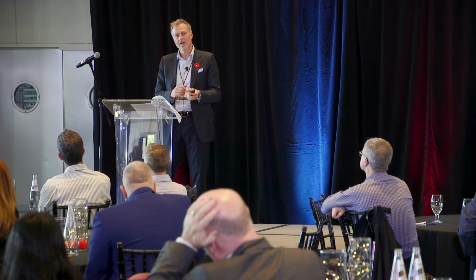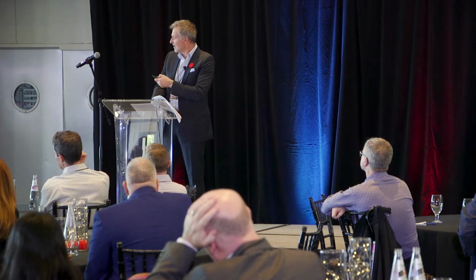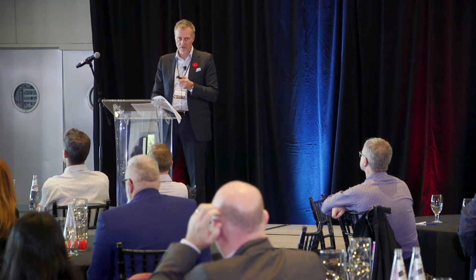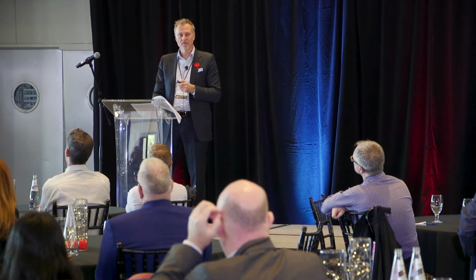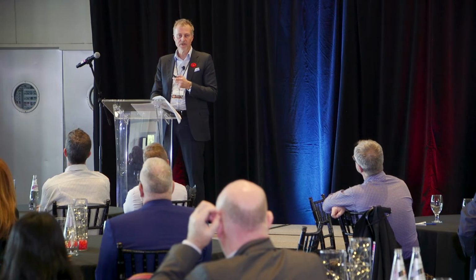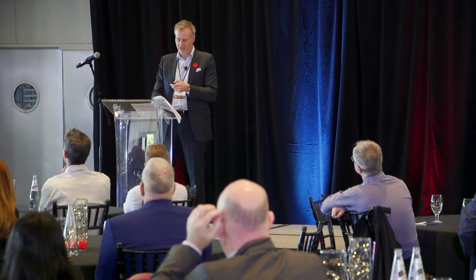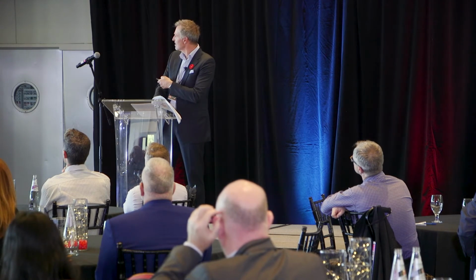And there could be times, depending on the complexity of the system, you may have the DP sensor at the most hydraulically remote load, but your pump will not then generate the head required at some low load situations, which would result in fan coils located closest to the mechanical room being starved. So engineers then will specify 2/3 of the run, and that's where they're trying to balance out the requirements for ASHRAE while still making sure that they're covering that scenario.